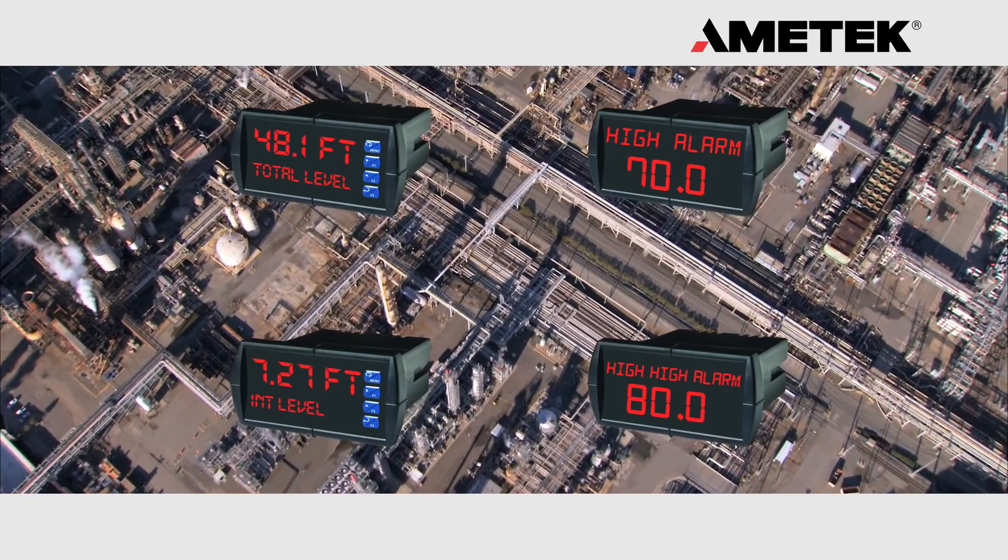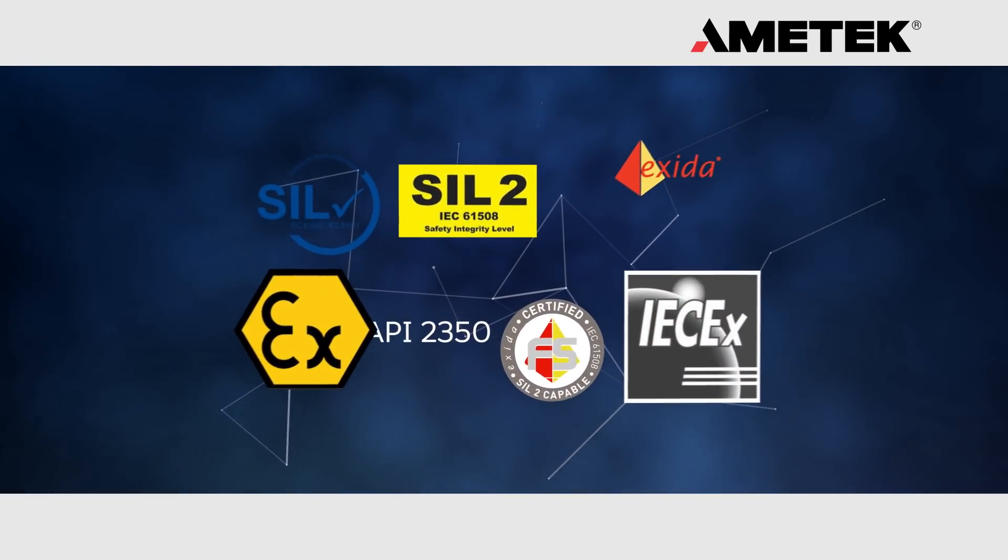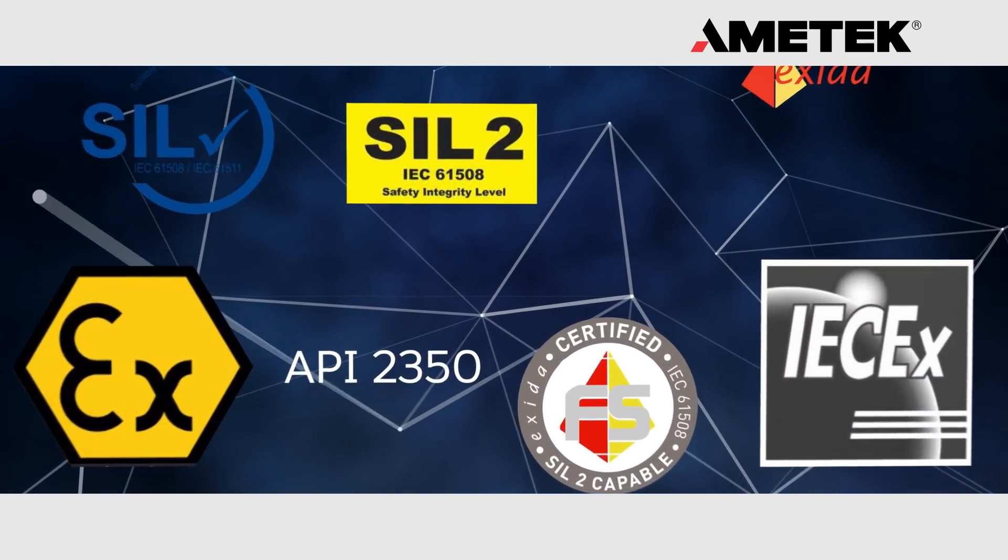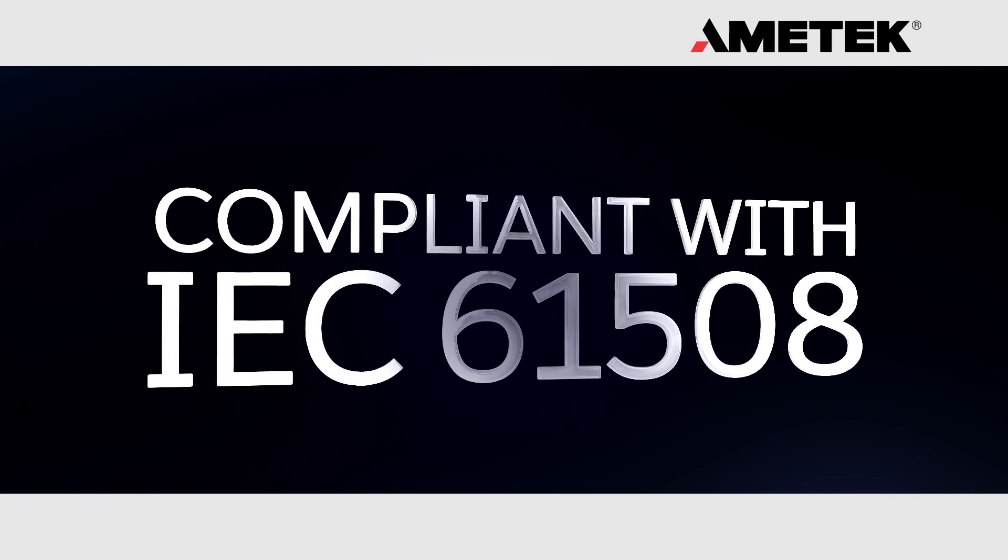Products used in this application are typically required to meet the API 2350 overfill protection standards, as well as SIL safety integrity level performance standards to IEC 61508.